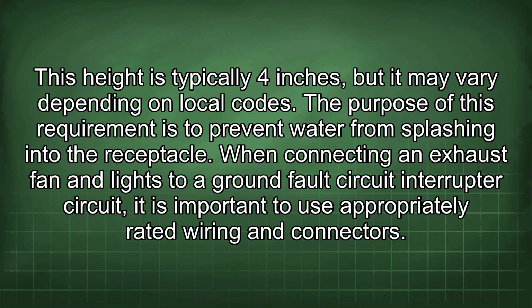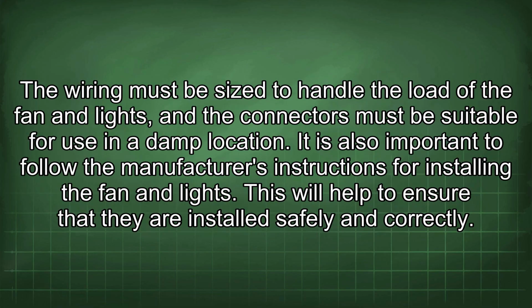When connecting an exhaust fan and lights to a ground fault circuit interrupter circuit, it is important to use appropriately rated wiring and connectors. The wiring must be sized to handle the load of the fan and lights, and the connectors must be suitable for use in a damp location. It is also important to follow the manufacturer's instructions for installing the fan and lights. This will help to ensure that they are installed safely and correctly.